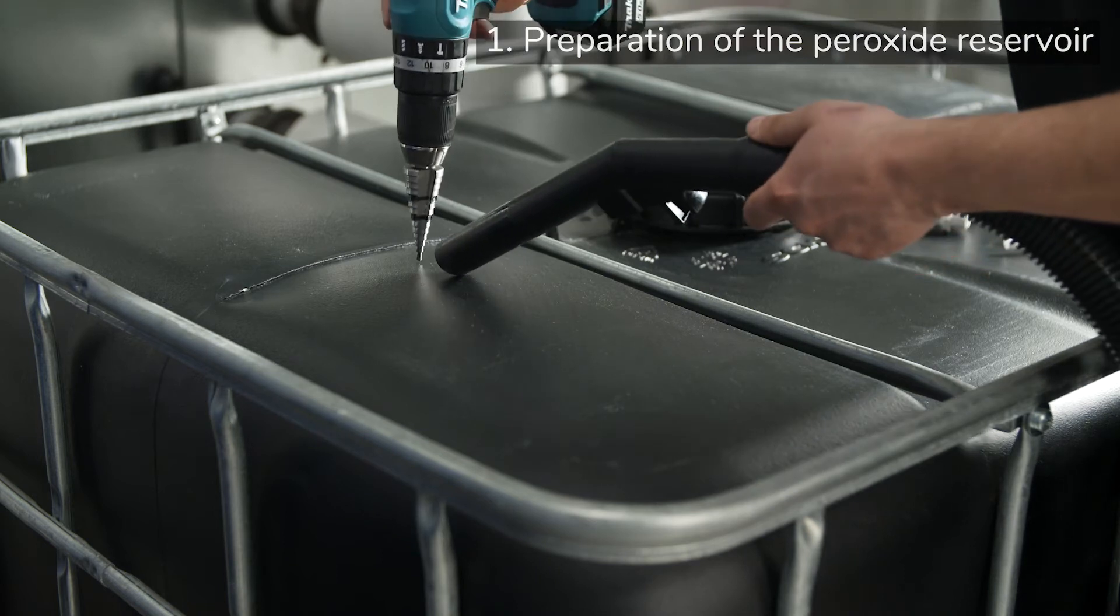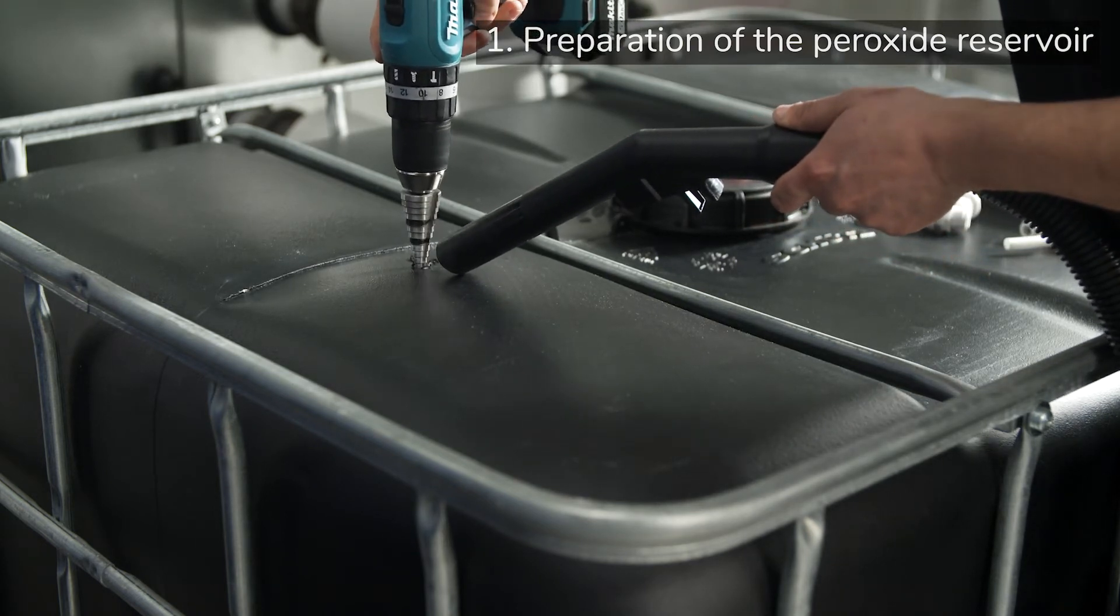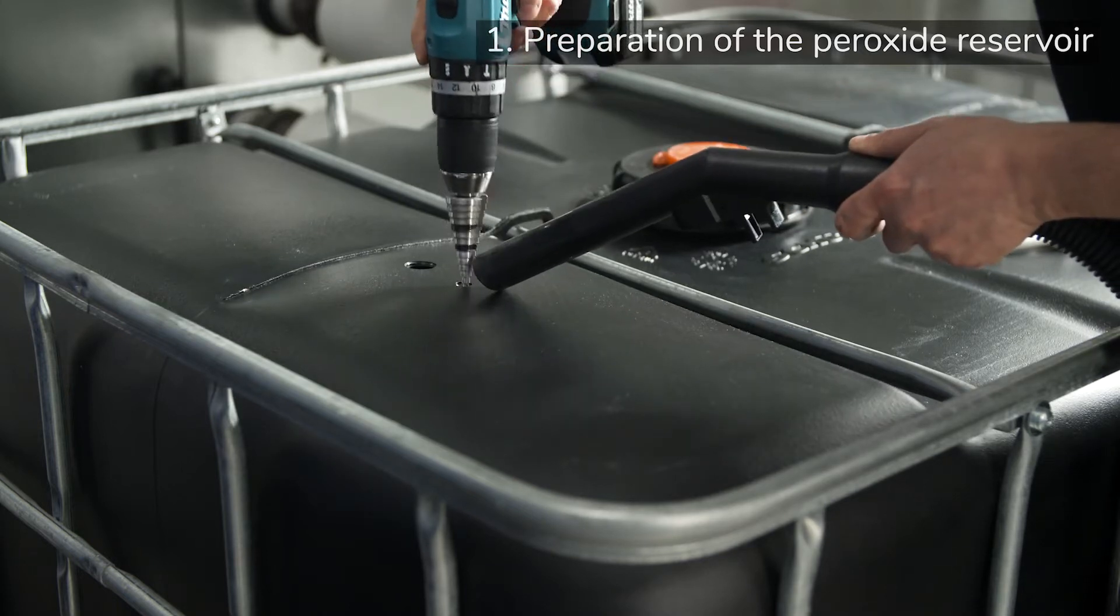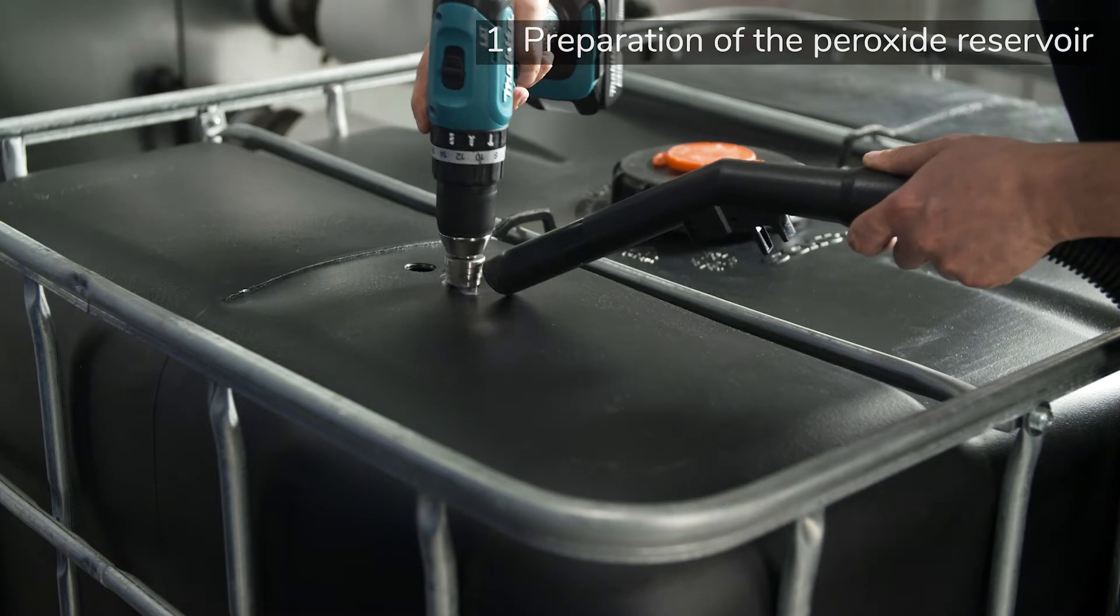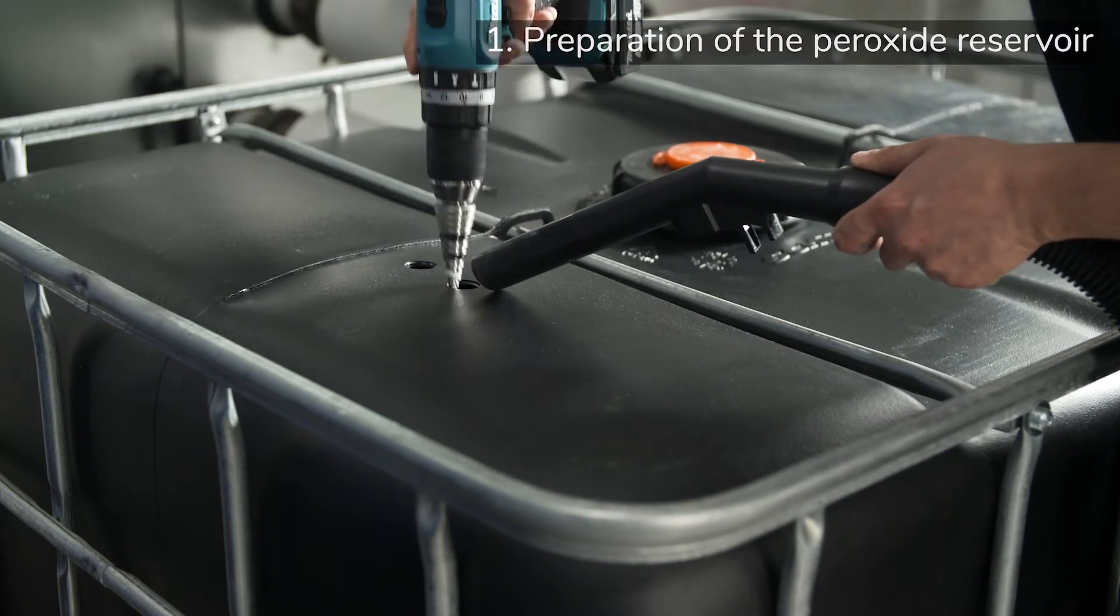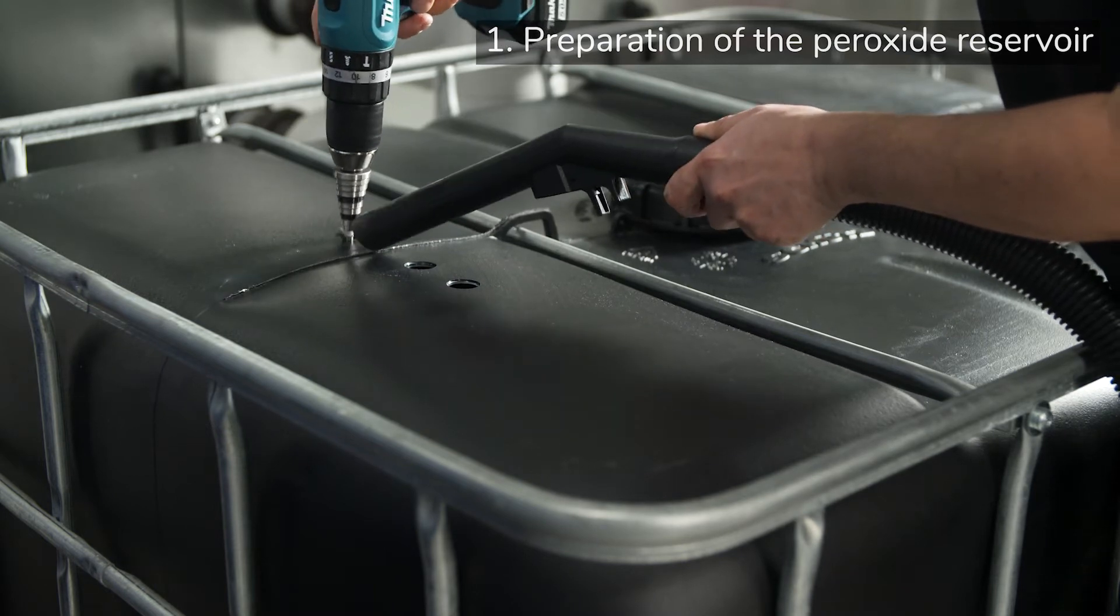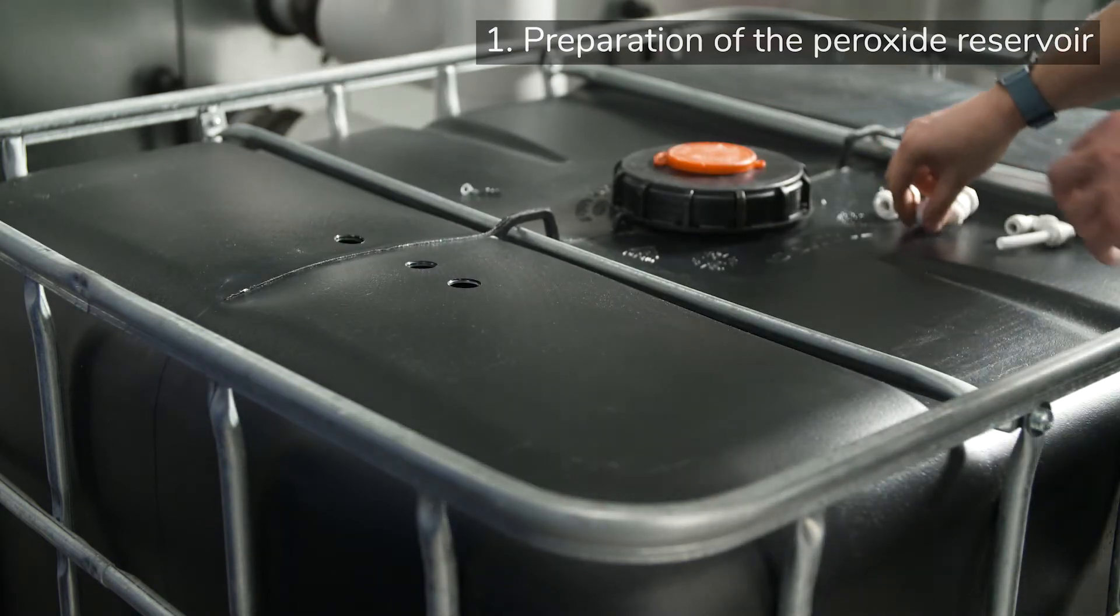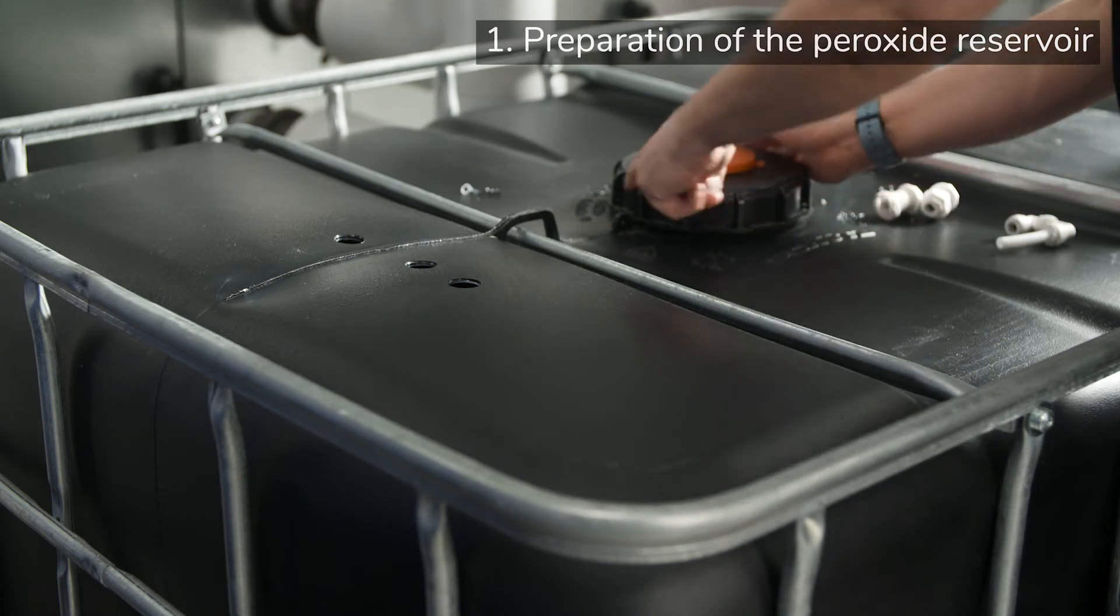Step 1. Drill three holes with diameter 22mm in the top part of the reservoir. It is important not to get residual plastic into the reservoir since it can clog the dosing pump later on. Here, we use a vacuum cleaner to remove the residue while drilling. One hole is for ventilation and the two others are for connecting tubing to the HP Gen cabinet.